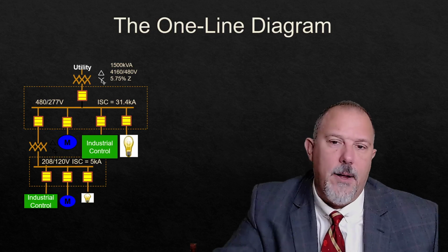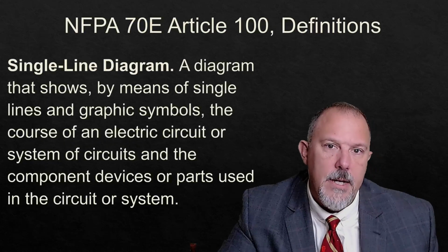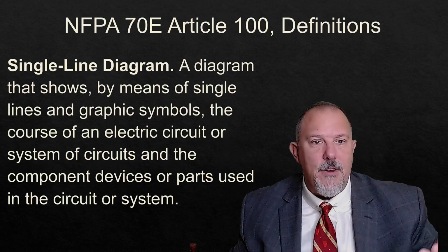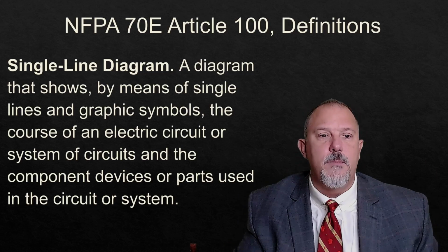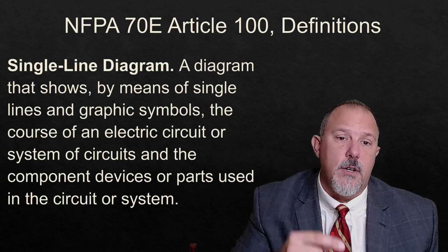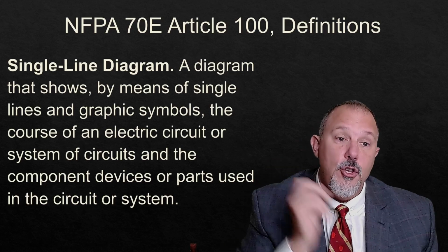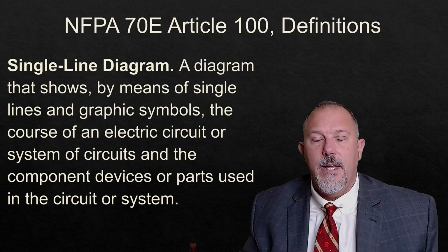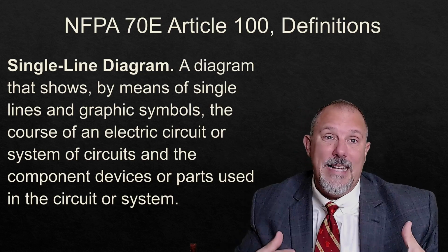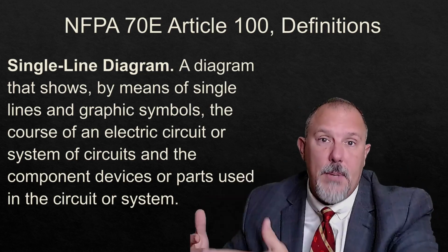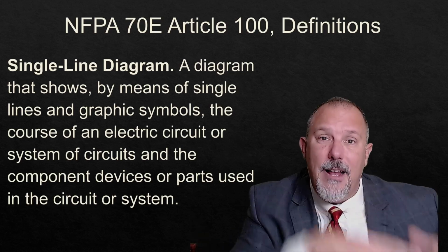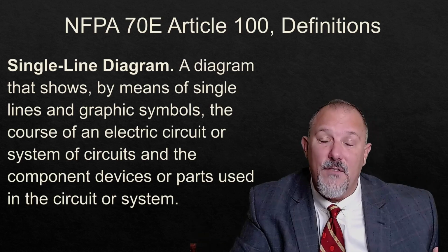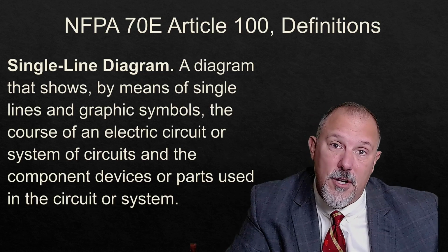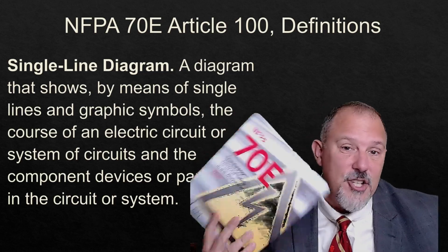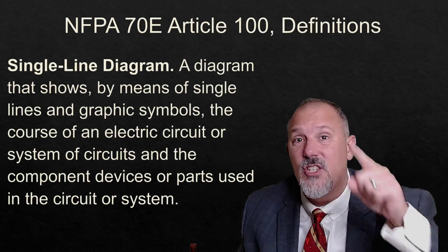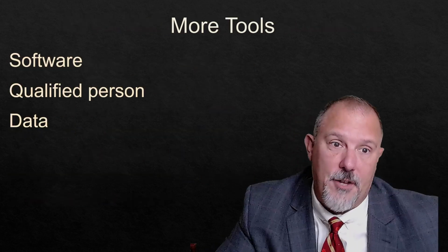The one-line diagram is a wealth of information. It's defined in 70E: a diagram that shows by means of single lines and graphic symbols the course of an electric circuit or system of circuits and the component devices or parts used in the circuit or system. It's an important piece of the puzzle. It's in 70E. It's referenced in 70B for maintenance. It's referenced in the National Electrical Code. And if you want to calculate fault currents to meet the National Electrical Code or calculate incident energy to get your PPE, you need this document, and it better be updated and accurate.